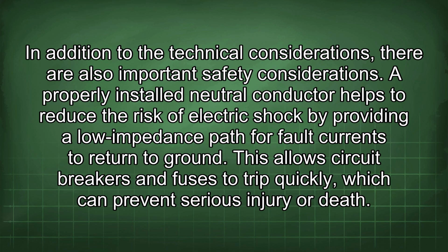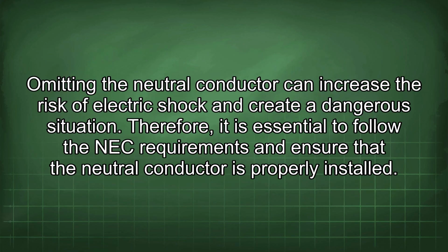In addition to the technical considerations, there are also important safety considerations. A properly installed neutral conductor helps to reduce the risk of electric shock by providing a low impedance path for fault currents to return to ground. This allows circuit breakers and fuses to trip quickly, which can prevent serious injury or death. Omitting the neutral conductor can increase the risk of electric shock and create a dangerous situation. Therefore, it is essential to follow the NEC requirements and ensure that the neutral conductor is properly installed.